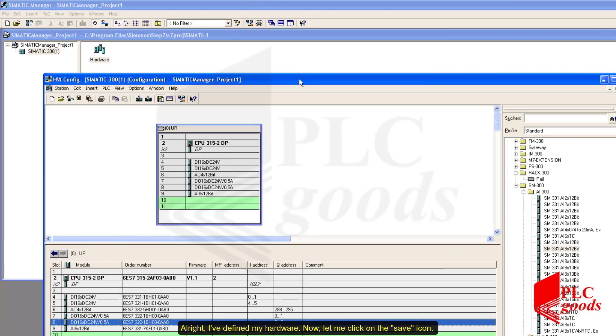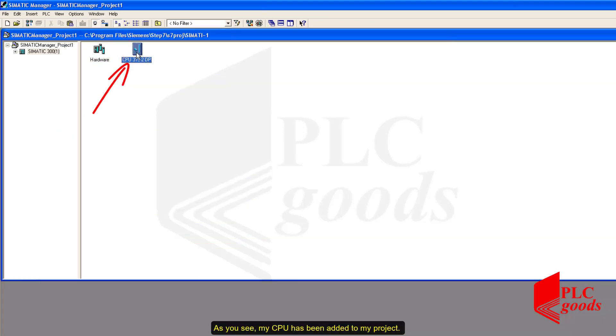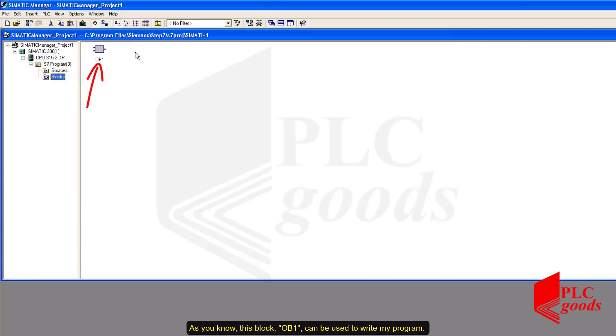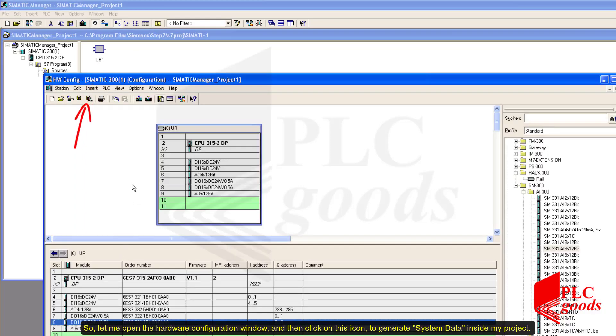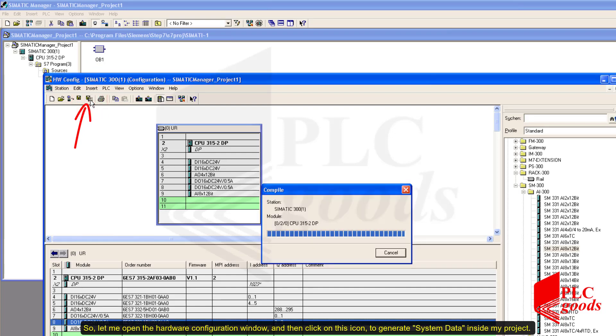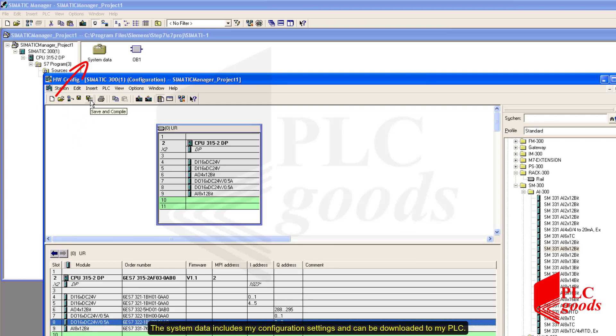I've defined my hardware. Now let me click on the Save icon. As you see, my CPU has been added to my project. As you know, OB1 can be used to write my program. Note that the hardware information must be downloaded as well as the PLC program. So let me open the hardware configuration window and then click on this icon to generate the system data inside my project. The system data includes my configuration settings and can be downloaded to my PLC.